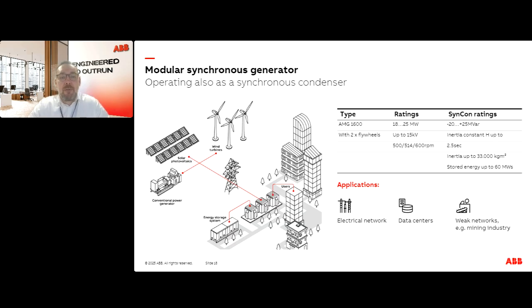So you need many times more inertia to have a reliable network. Because you have solar and wind, if we think about how they produce energy, when the sun is shining, you don't need this conventional power during those times, other than for peak saving applications. But you need it to balance out the fluctuations of the power supply from the renewables. So the benefit here is that when you can run this new generator as a synchronous condenser, you can use it to balance the grid or support the grid with more inertia and also reactive power. It can be either consumed or produced depending on the need.